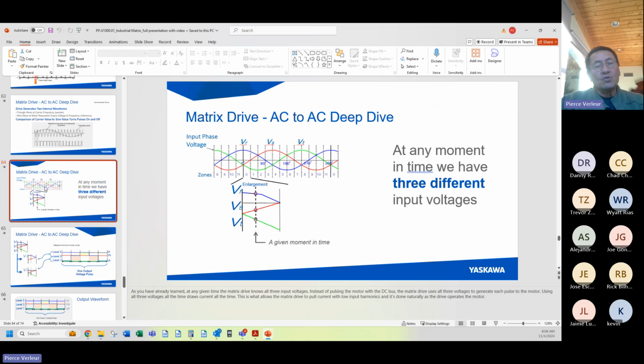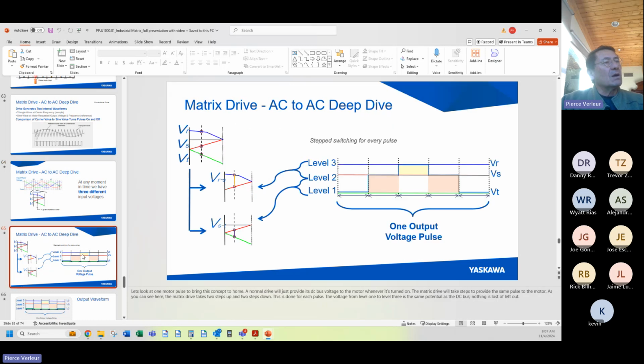The matrix drive, as I said, we switch directly from the AC line to the motor. Here's the AC line, three-phase power, green, blue, red. At any instant in time, I can choose from 3 different voltage levels. And in this enlargement here, I have VR to VS, VS to VT, and VR to VT, 3 different amplitudes. So in addition to pulse width modulation, I have 3-level pulse amplitude modulation available to me. And therefore, we never full height switch the pulse because we want to avoid that dVdt.